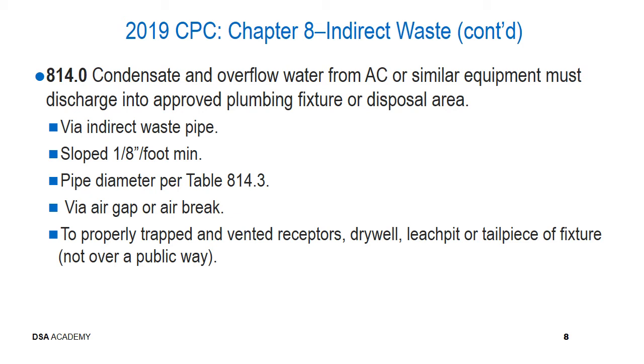It's also important to understand that it is never acceptable for any type of AC overflow water or condensate to discharge into the storm drain. It is acceptable that it discharges into the building drainage, however.